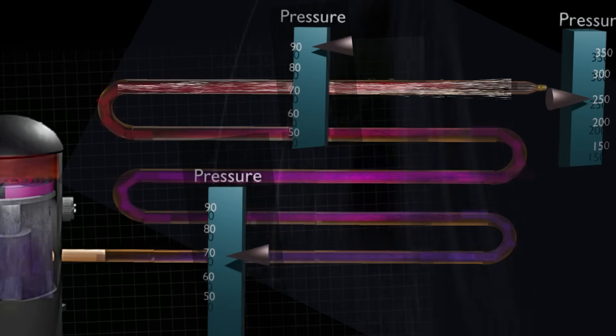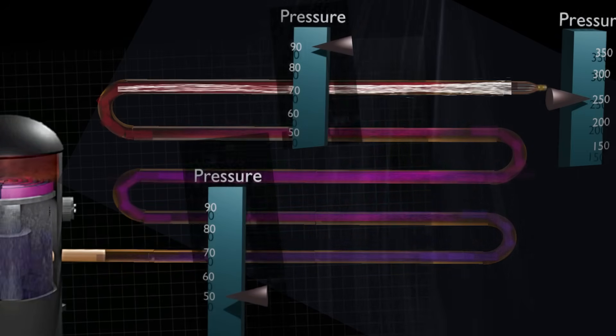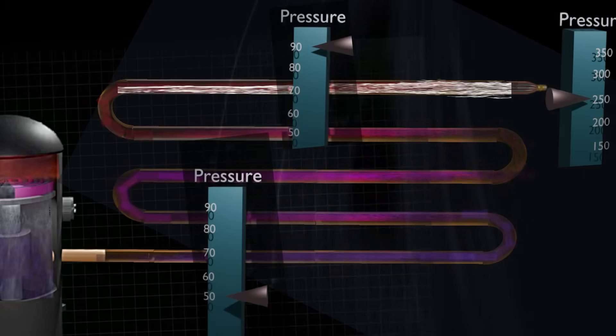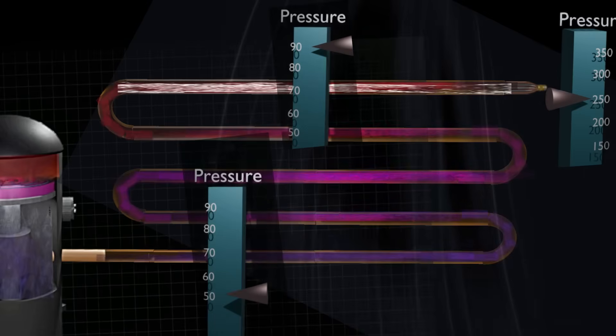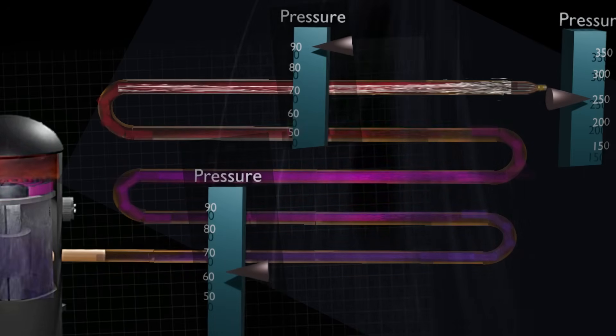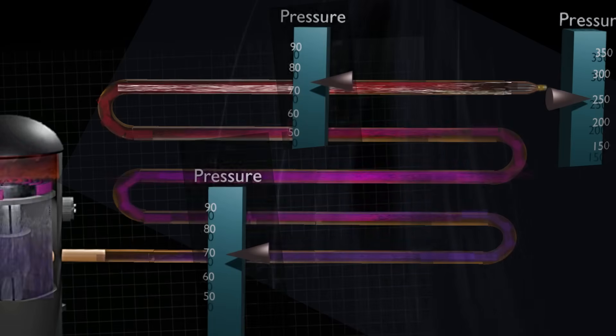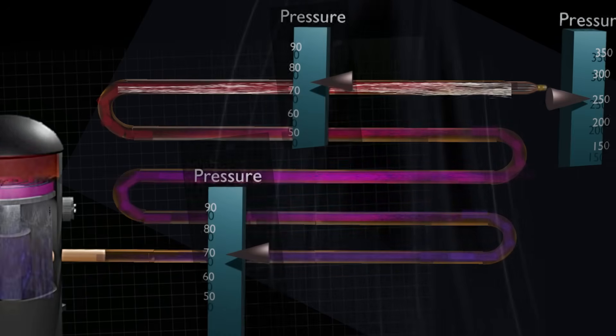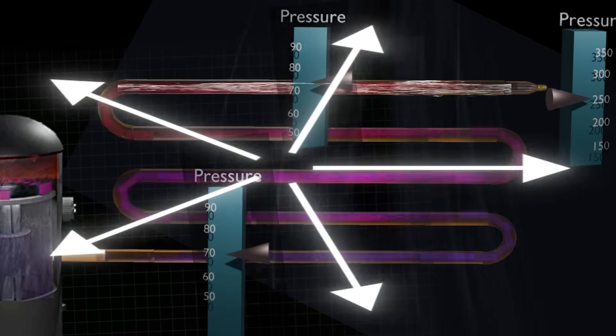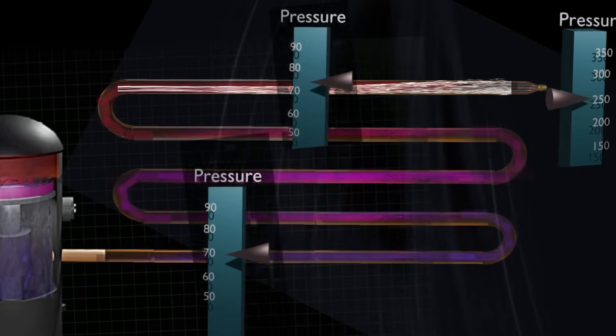On the other side of this bottleneck we have a dropping pressure, because we're not feeding enough refrigerant into that area. Meanwhile, heat is still flowing over the evaporator coil, so that highly dense liquid region early in the coil is going to eventually pick up enough heat to start boiling, and that's going to generate a great amount of pressure that starts rebounding the pressure in the later part of the coil. Eventually vapor starts making its way into the rest of the coil, but the key difference here is that the vapor part of the coil is going to be very dense — a high-density, high-mass vapor region. Because of that, more refrigerant is able to absorb more heat and spread it out over a larger area, so the temperature of the refrigerant doesn't climb rapidly like it would in a long vapor section with very low-density vapor refrigerant.